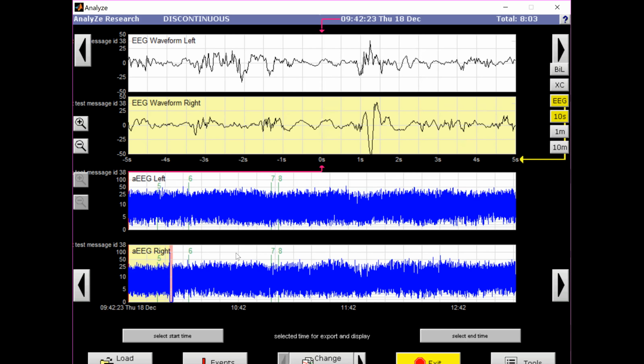If you're using a full EEG monitor, everything is modifiable. So you will sometimes find that the aEEG is not set to the right time scale, and it will look very patchy. It will almost look like status epilepticus, where it has those breaks. So make sure that if you're using a full EEG, they have set the time scale to 6 centimeters per hour so that it will be standard for you.